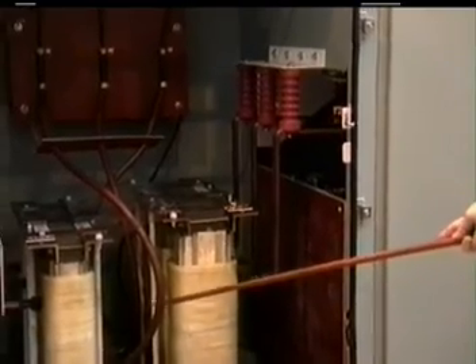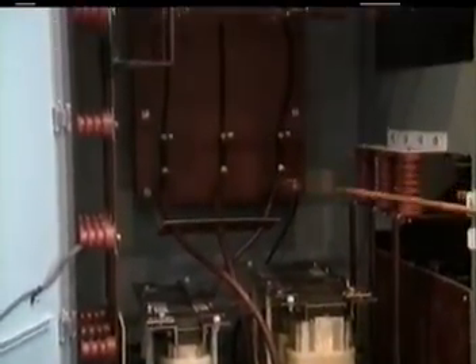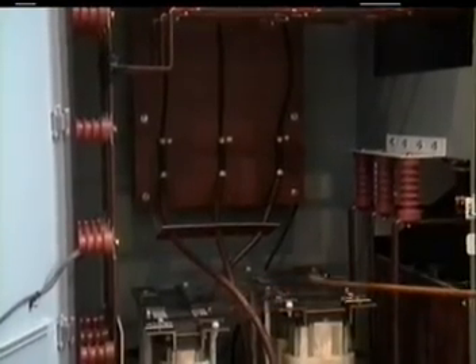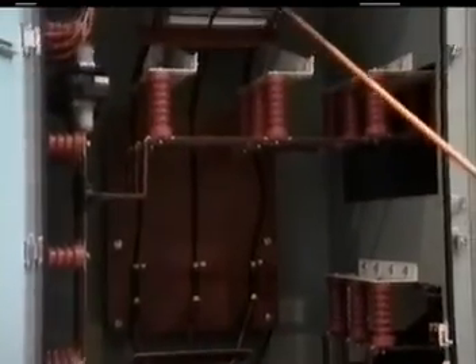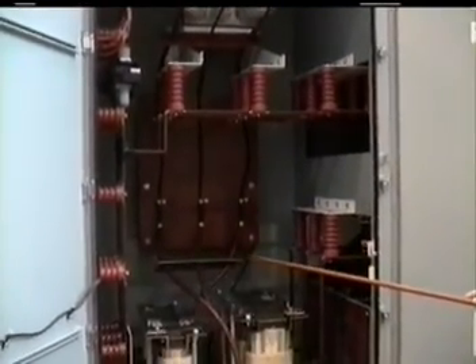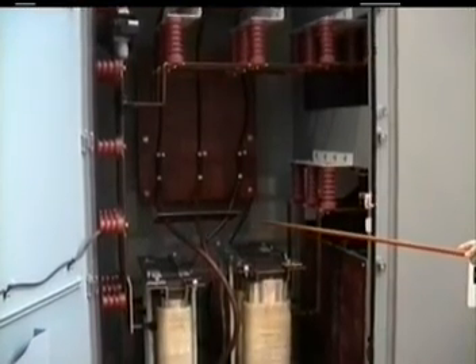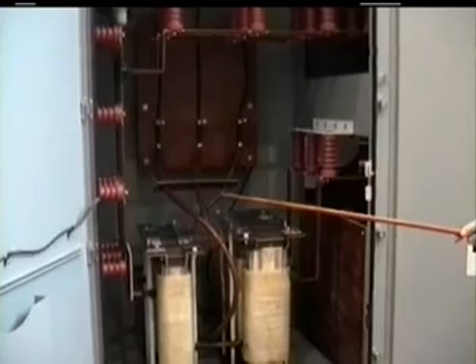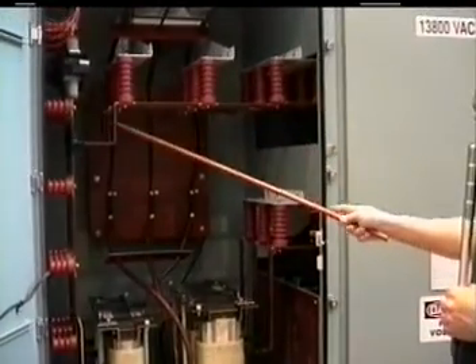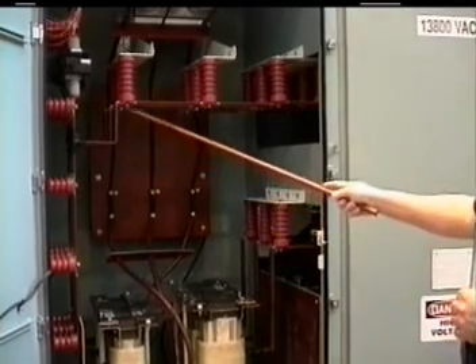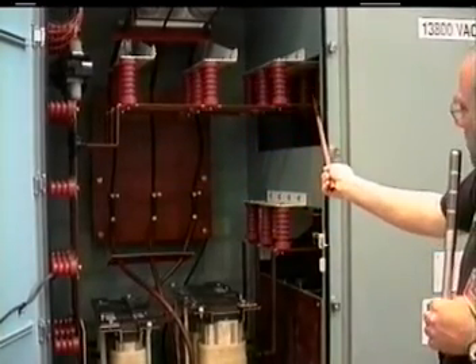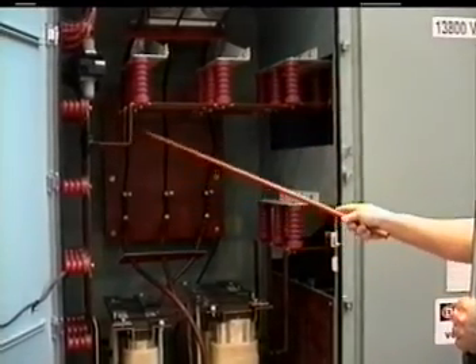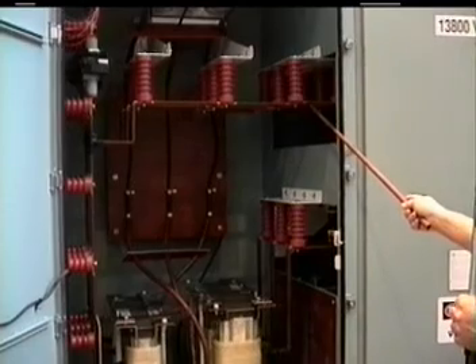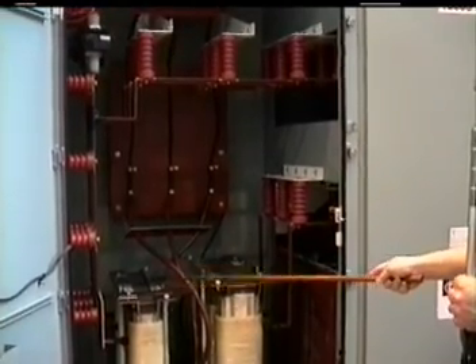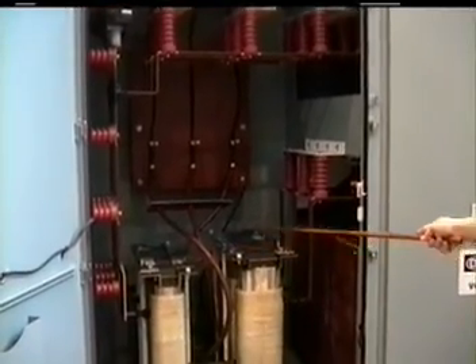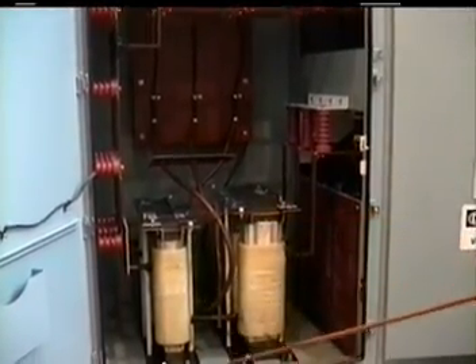In the middle of the inductors is an RC filter, and the combination of the input reactor, output reactor, resistor, and capacitor form a filter section that provides the dv/dt as well as the di/dt protection for the solid state section. Whenever the starter is fully operational and the bypass contactor picks up, which is taking off at this point of the bus and comes along here to the input of the bypass vacuum contactor, it provides for a run bus circuit during normal operation. It effectively bypasses the filter section, and yet the filter section is still actively in the circuit, providing additional transient protection for the equipment.